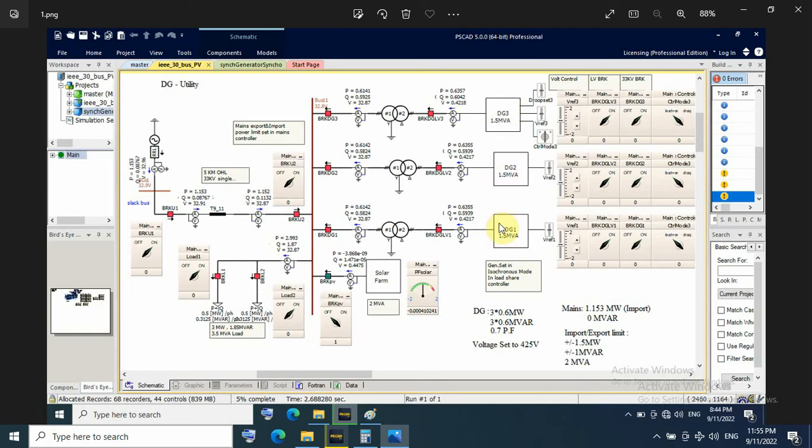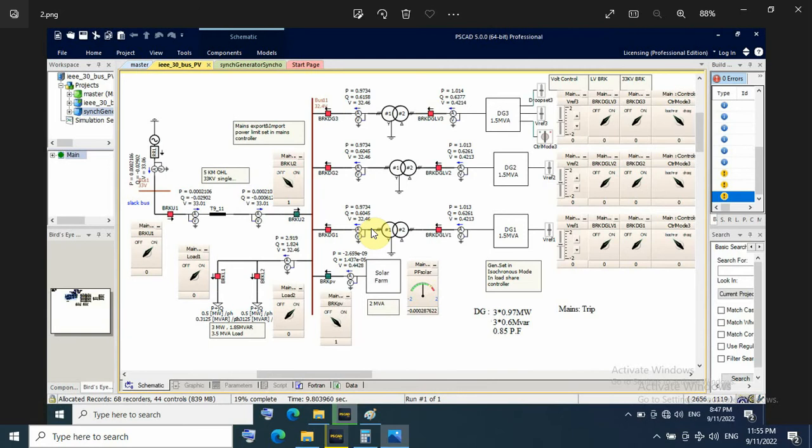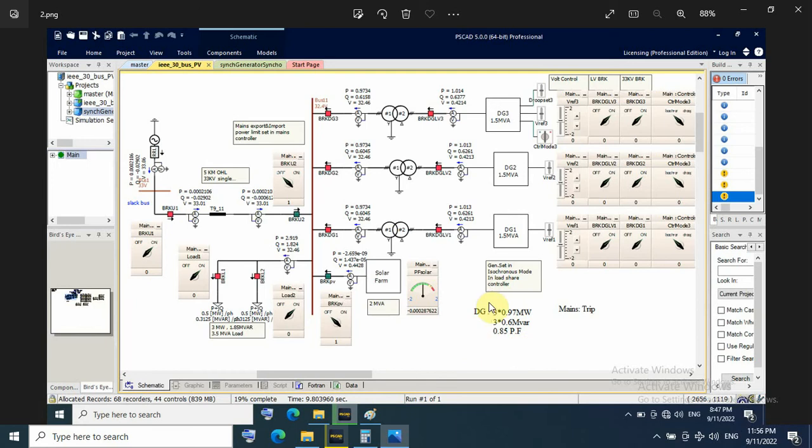The DG gensets running in isochronous mode and I have module for mains monitoring. Here in this case the mains breaker trip for any external force or another issue. The DG loading about 1 megawatt and 0.6 megavar. That means at 0.85 power factor.